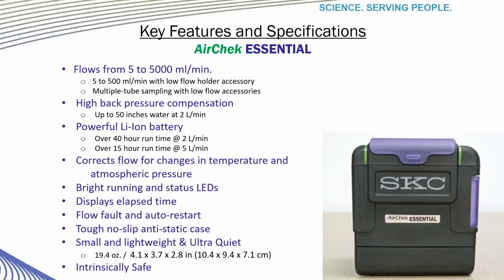The pump corrects the flow to compensate for changes in temperature and atmospheric pressure, even though it is a quote-unquote basic pump. In addition to that, the bright LEDs of the AirChek Touch and Pocket Pump Touch have been a big hit with our customers, so we have included them on the Essential as well. It has a very large displayed elapsed time clock. The clock will freeze upon a flow fault, but if the pump auto restarts and clears the blockage and is able to reestablish the flow rate, the clock will resume and help achieve a valid sample.